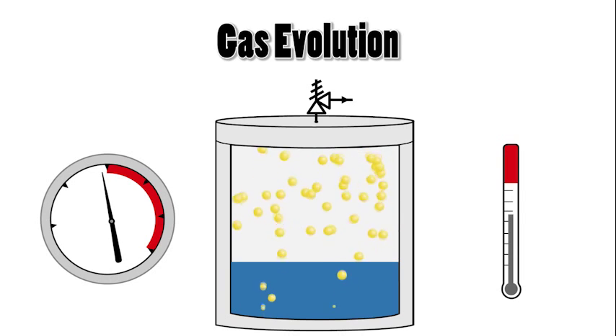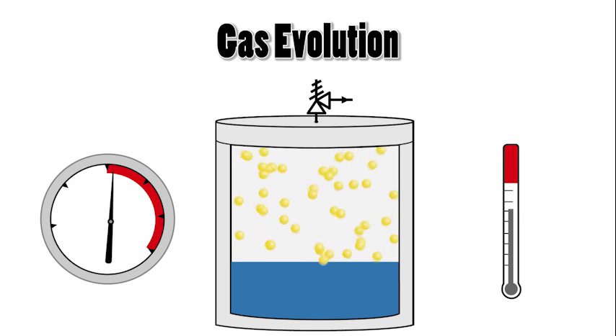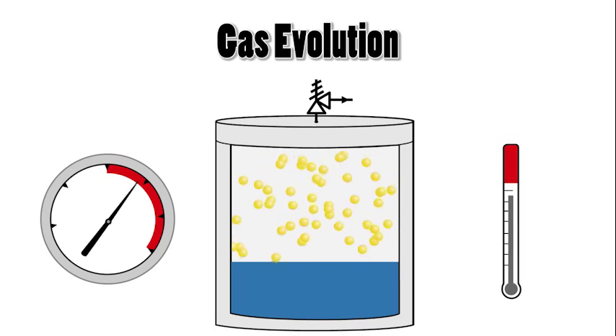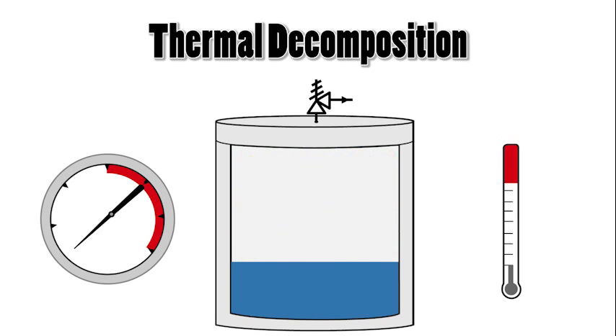Rising temperature adds non-condensable gases to the headspace. The resulting pressure increase is a function of both temperature and the initial loading charge. The chemical decomposition of samples or gases under elevated temperature and or pressure can increase the number of moles in the headspace very rapidly. When all parameters are known, the internal pressure increase can be calculated or gleaned from reference material.